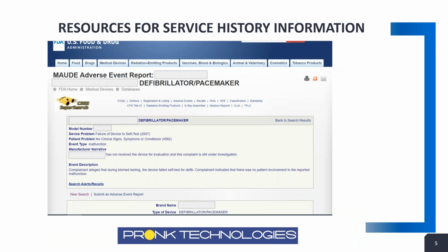One example here, just to give you a brief overview of what the page would look like. This is an example of a report. We took away manufacturers' names, not wanting to highlight any particular manufacturer. All medical devices have issues reported to the FDA, so it's not unusual that it happens. It's a centrally located database that allows us to share information and to have a good vision into what could be happening in the field with these devices.